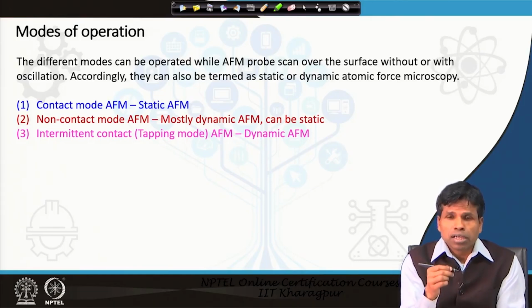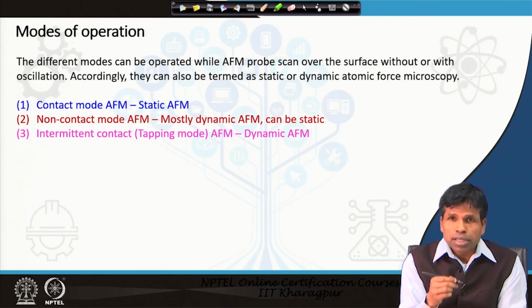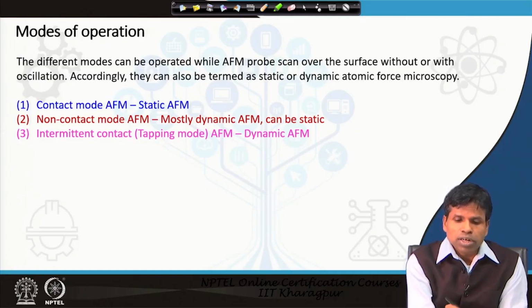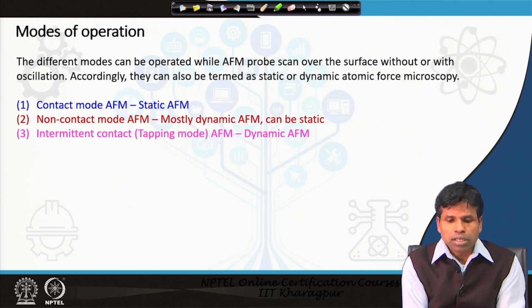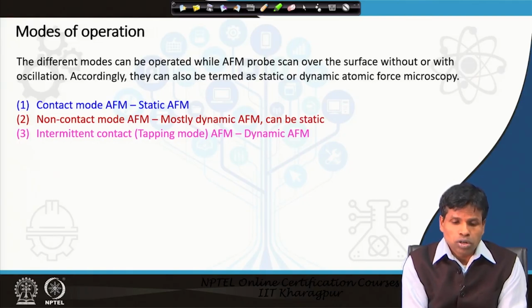On the other hand, in non-contact mode and intermittent contact mode, the tip will be oscillating above the sample, and as it oscillates above the sample, we say it is a dynamic mode of operation. And non-contact mode can have dynamic, can have static also. In some cases, static measurement is done, but mostly it is done with a dynamic mode of process.